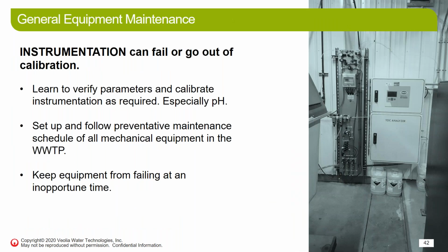So just in general, instrumentation as well is something you should be checking. It can fail or go out of calibration. So calibrate your instruments on some frequency, during operation or when you're down. pH is usually the biggest one you have to work on a lot. Those typically go out of calibration pretty easily. A preventive maintenance schedule for all your equipment, your pumps, your valves, your instrumentation, that's all very important. It's good to keep all that equipment from failing at an inopportune time.